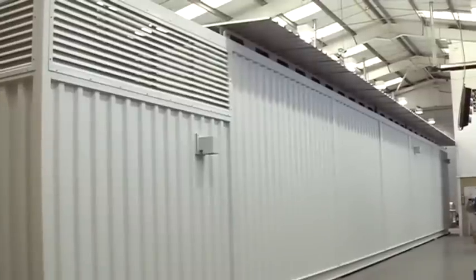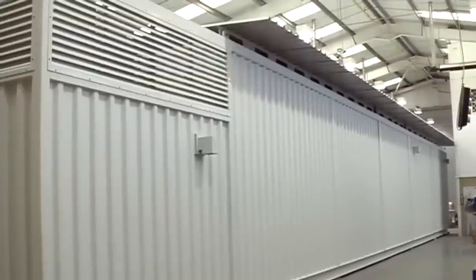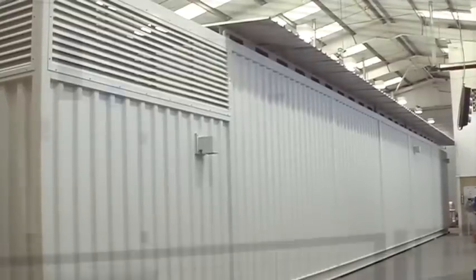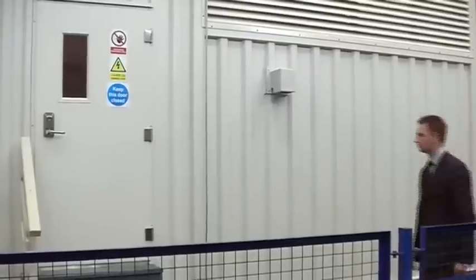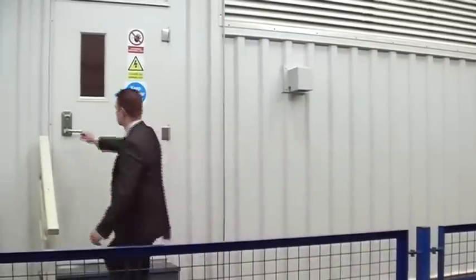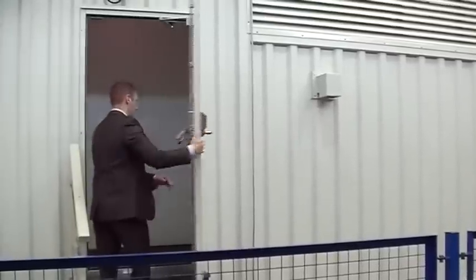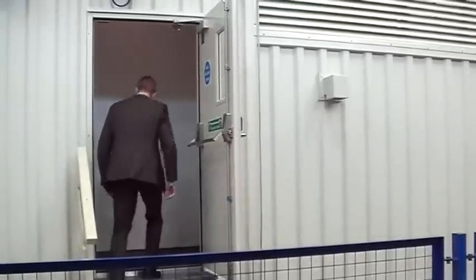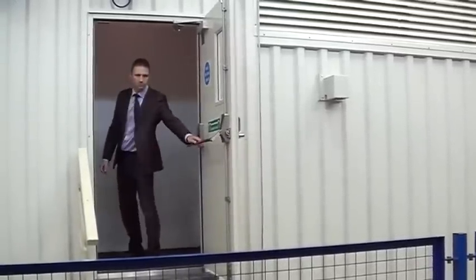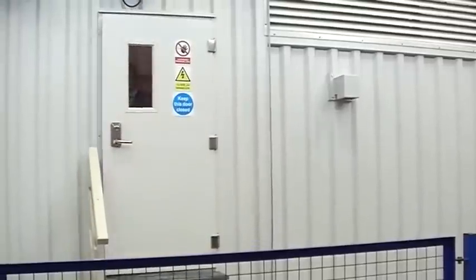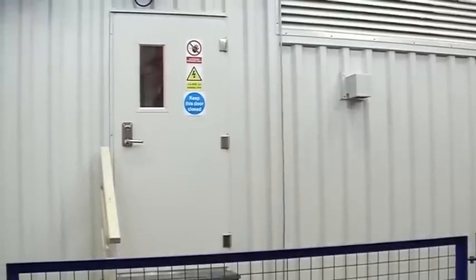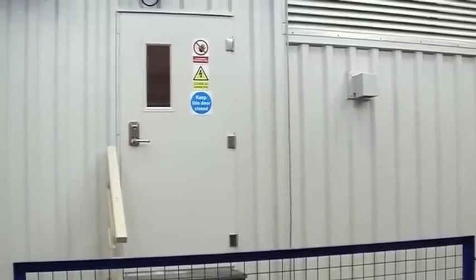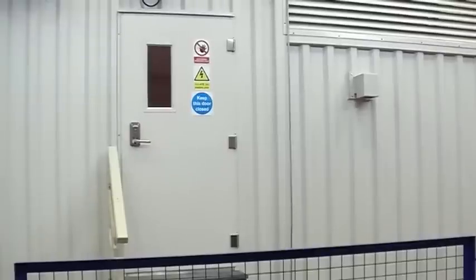A detachable sunshade provides an air gap above the LER, helping to reduce solar gain. The personnel entry to the LER is via an airlock lobby. The airlock provides additional protection against the ingress of sand, dust and gases. All doors are fitted with emergency exit furniture that can be overridden with the doors locked, and all external doors are fitted with stainless steel handles and hung on stainless steel hinges.